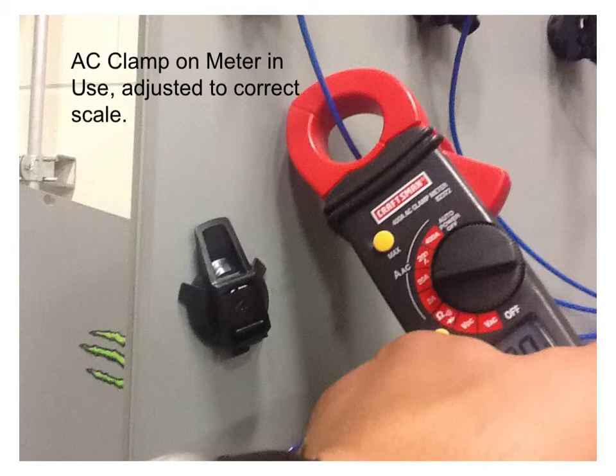Here's a nice shot of the AC clamp-on meter in use. Notice here's my blue conductor. I've inserted and I've clamped the clamp-on meter around the conductor. Again, we can't see it, but we've got that magnetic field that is surrounding that conductor. It's being picked up by that meter.